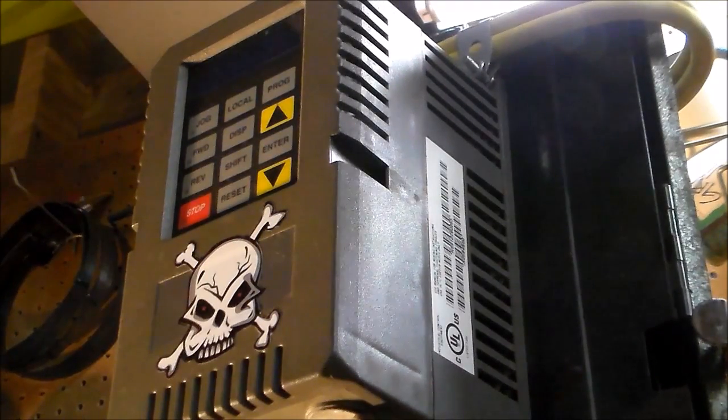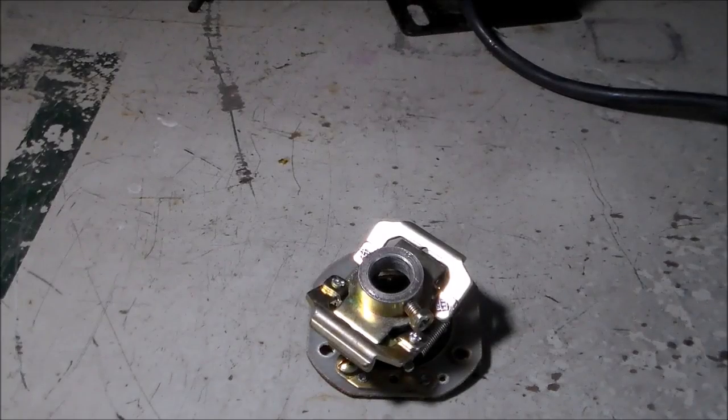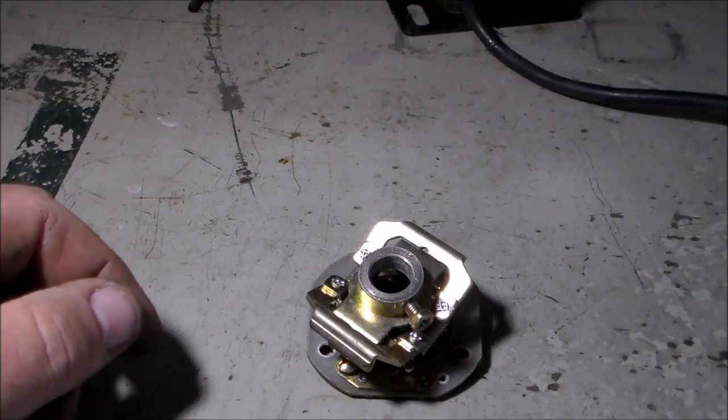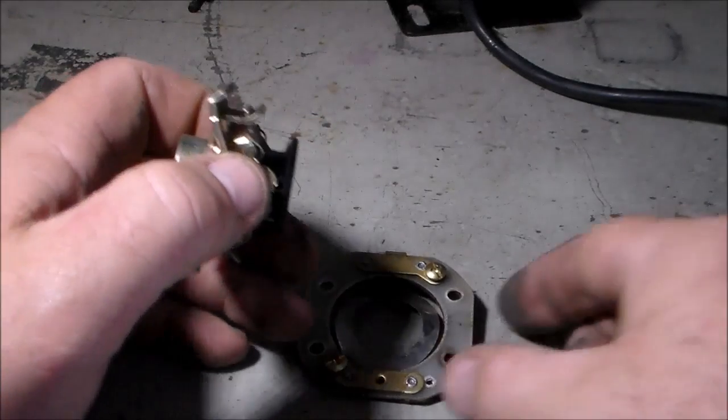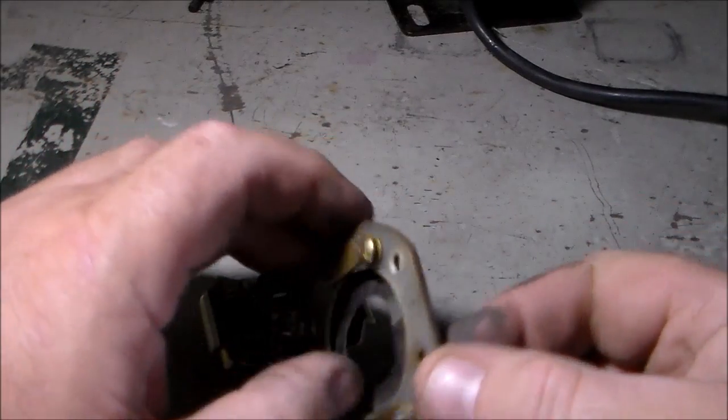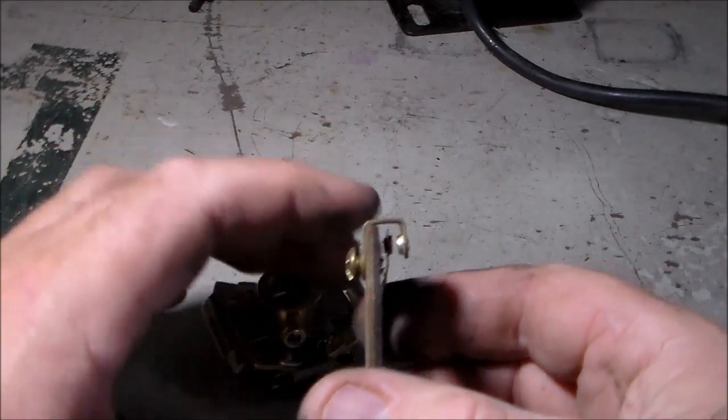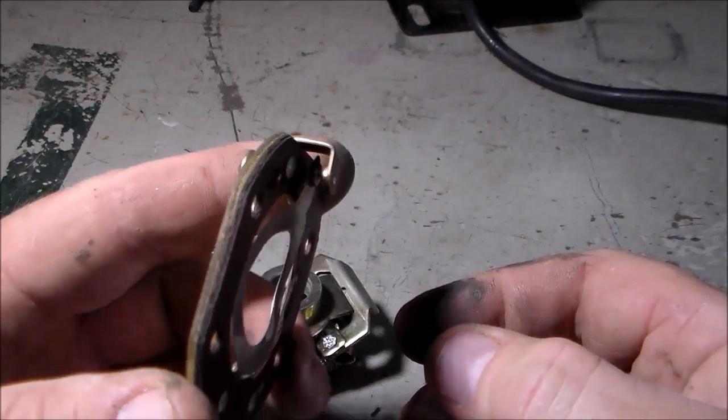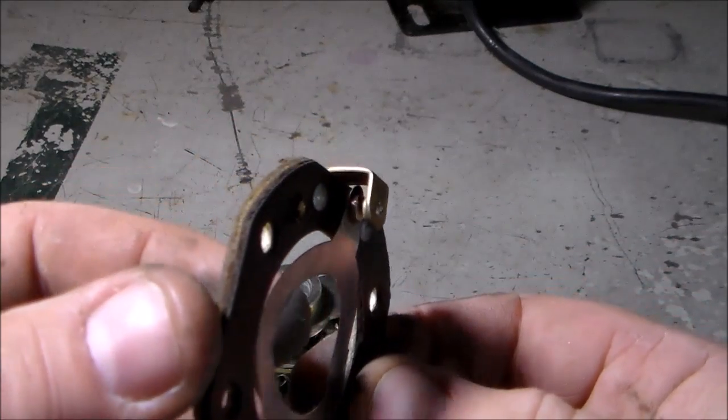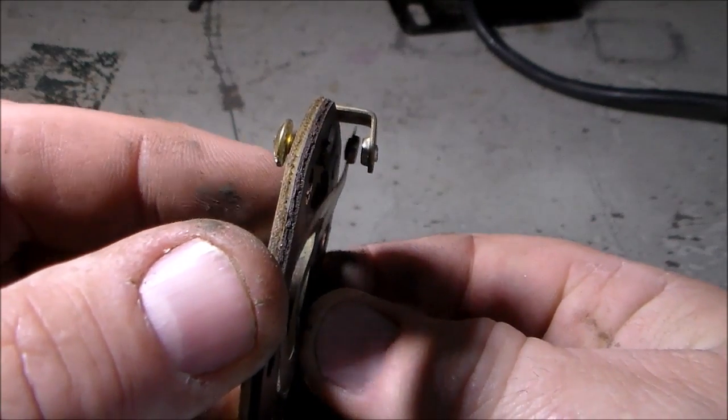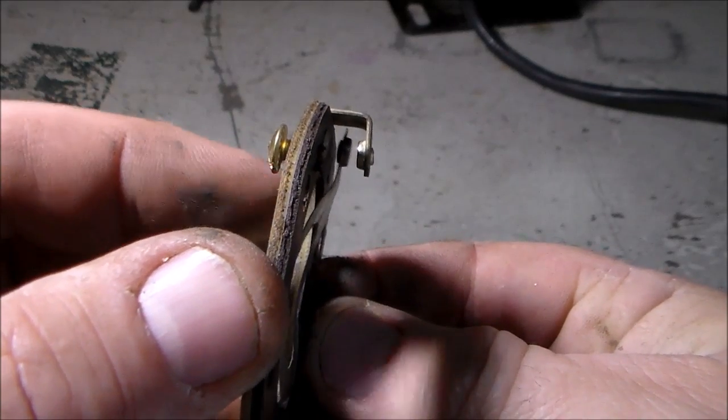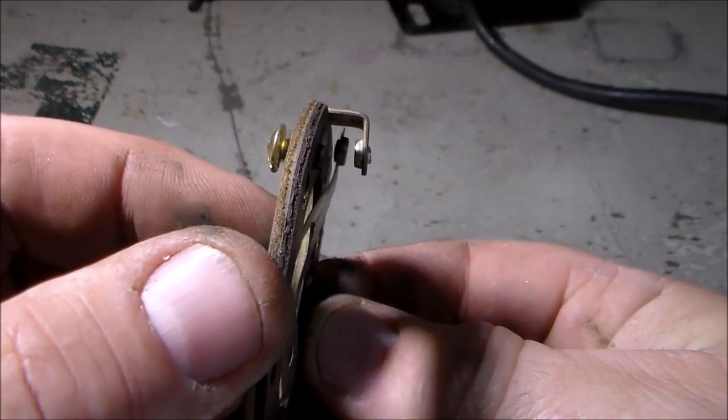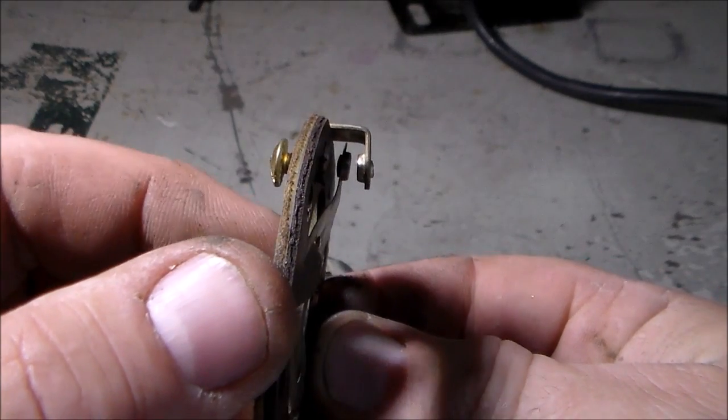So anyway, on with the update part of this video. I had a few questions about my first video. In this part two, I was going to maybe expand a little on something I had tried to explain not so well. This is the centrifugal switch that had caused me the motor problems in the first video. You can see this piece inside how it moves, contacts. And I think I mentioned it reminded me of the points on an old car.